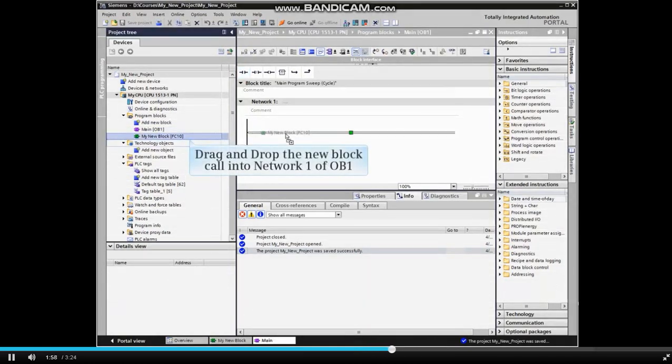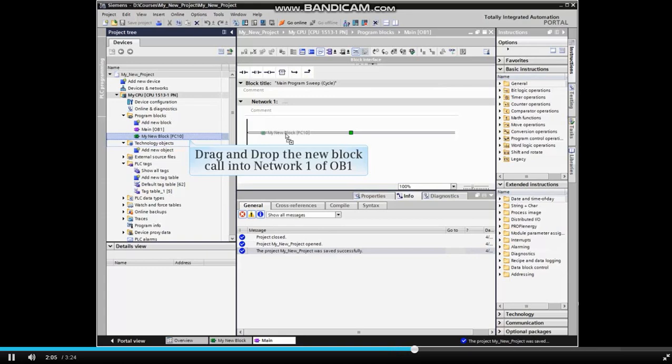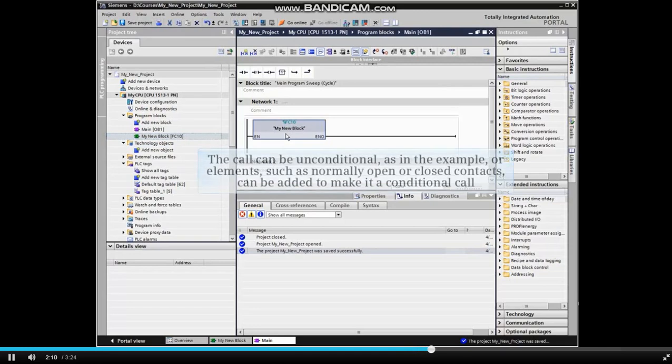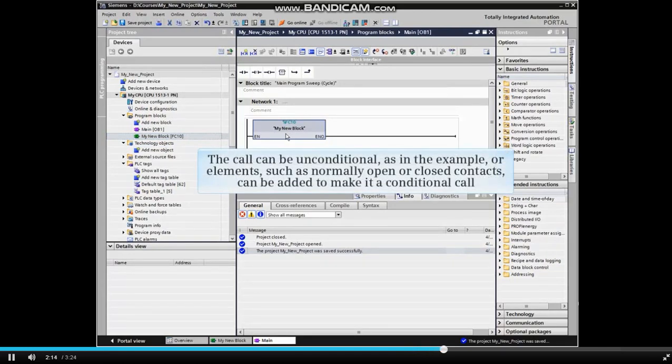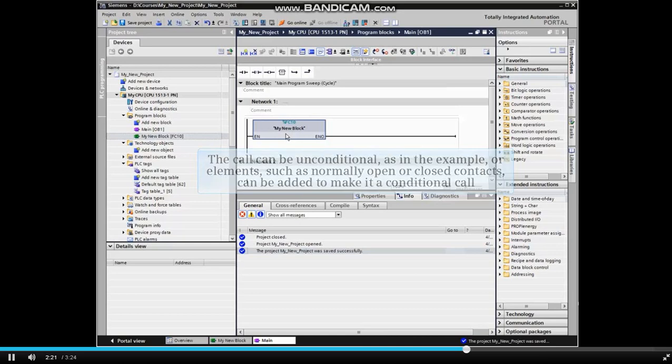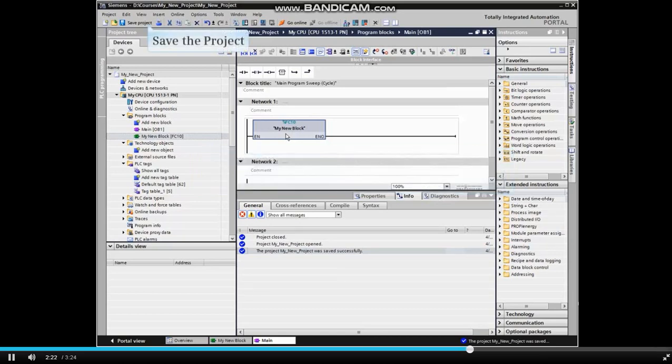Under program blocks in the project tree, locate the new block, highlight it, and drag it onto the desired network. Drop the block on the line to create the call. The call can be unconditional, as in the example, or elements such as normally open or normally closed contacts can be added to make it a conditional call.